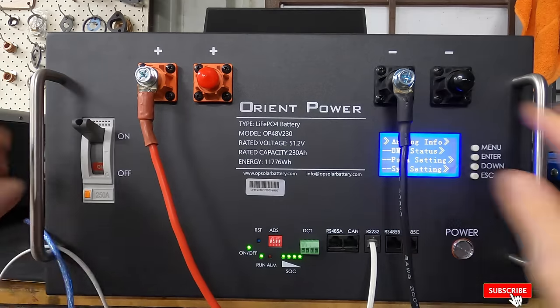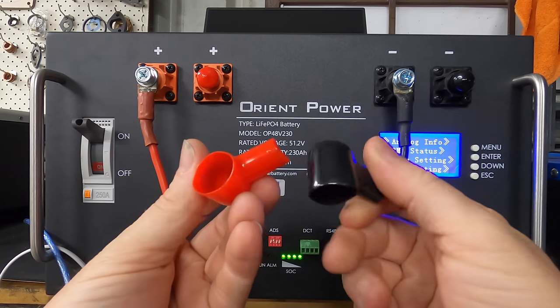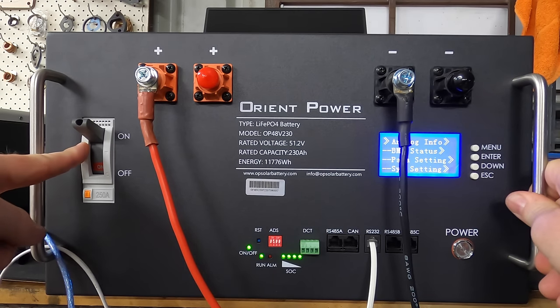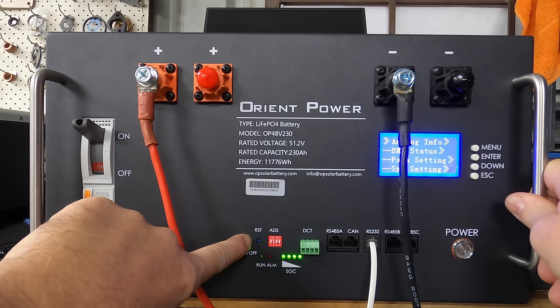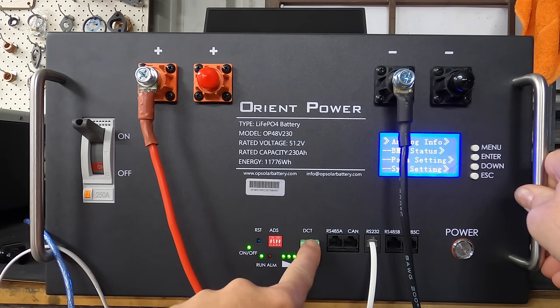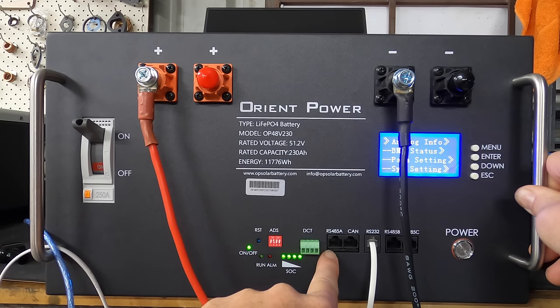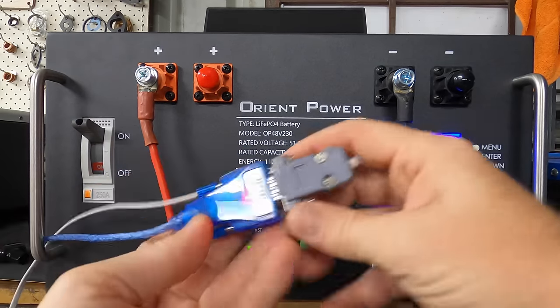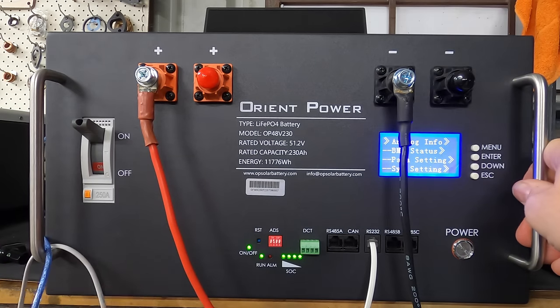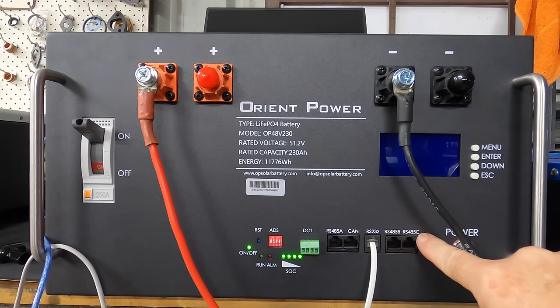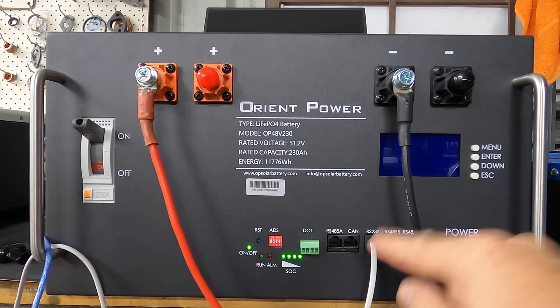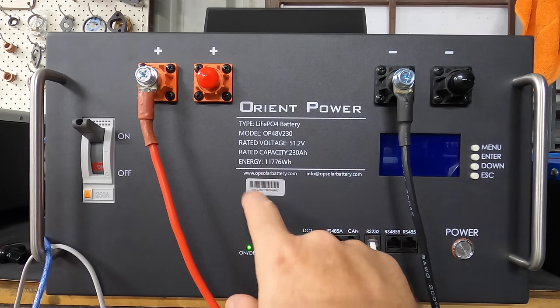Having a quick look at the little control panel on here we've got the positive and negative terminals, a 250 amp breaker, an on/off indicator, a reset switch, and an address switch so you can have multiple of these batteries all running under one battery management system. We've got alarm, state of charge, DCT which is dry contact points, RS485A, CAN bus, RS232 which goes into a USB adapter for the computer, and RS485B and 485C which link up if you have multiple batteries so the battery management systems can talk to each other.